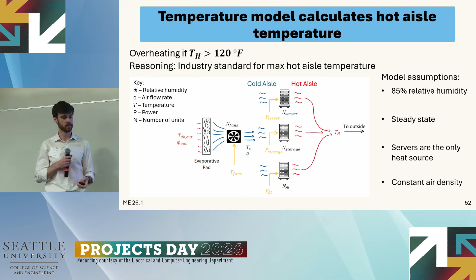We are again assuming steady state for the same reasons outlined previously, and we are going to say that servers are the only heat source. So because we're trying to calculate this hot aisle temperature, we don't care about heating from lights or, say, the toaster turning on in the break room. We're going to throw all that out and just focus on the servers. And then finally, we're going to assume constant air density. In reality, the density of air will change as the temperature changes, but it's a very small change, so we're putting that aside as well.